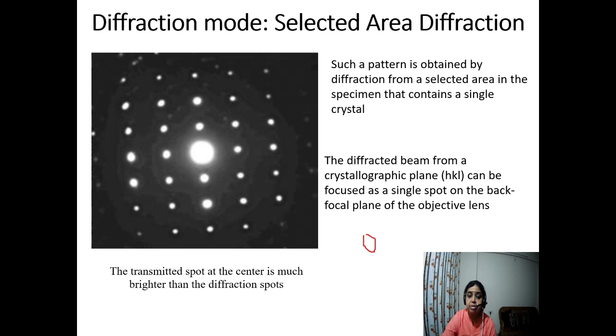Now in this also there are two kinds of images, bright field and dark field. As I mentioned, for this kind of images we use elastically scattered electrons. For conventional imaging we use inelastically scattered electrons in conventional TEM, and for dark field and HRTEM, high resolution TEM, we use elastically scattered electrons. Again there are two modes, bright field and dark field. What is bright field? Suppose these are your back focal points, and this is our objective aperture. If we allow the transmitted beam, your central spot, to pass through, this is your bright field.